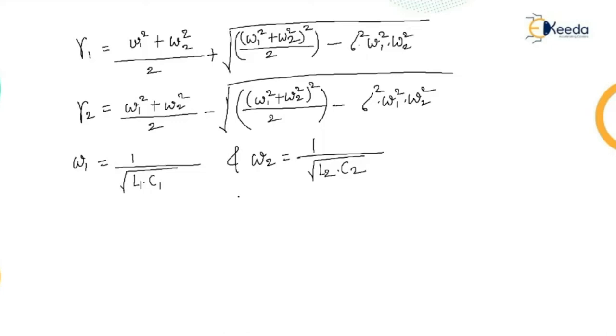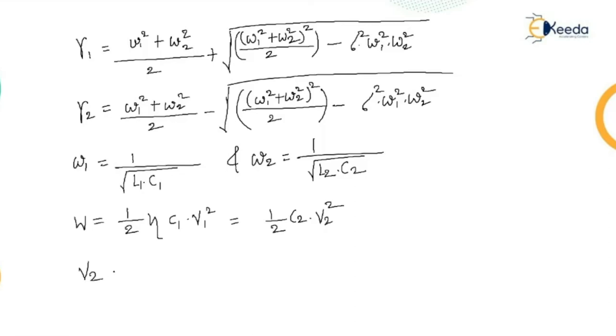From the energy perspective, the efficiency η can be represented as: W = (1/2)·η·C1·V1² = (1/2)·C2·V2², which gives V2 ≈ V1·√(η·C1/C2). It can be shown that if the coefficient of coupling k is large, the oscillation frequency is less, and for large values of the winding resistances and k, the waveform may become a unidirectional impulse — as will be discussed in the next section on switching surge generation.